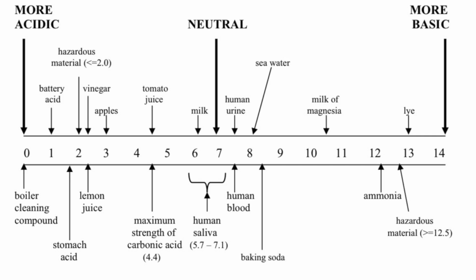Now let's quickly look at the pH scale for the central heating water. In order to minimise the corrosion of the boiler hardware, the pH in the feed water, or the central heating water, must be controlled within a narrow range. Too low a pH will result in excessive corrosion of the iron components, while too high a pH will result in attack on the copper containing parts.